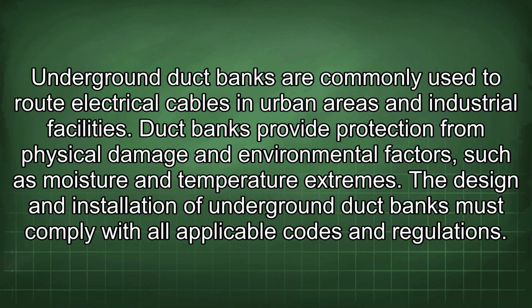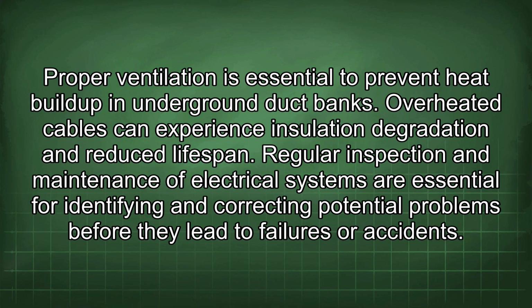Underground duct banks are commonly used to route electrical cables in urban areas and industrial facilities. Duct banks provide protection from physical damage and environmental factors, such as moisture and temperature extremes. The design and installation of underground duct banks must comply with all applicable codes and regulations. Proper ventilation is essential to prevent heat buildup in underground duct banks. Overheated cables can experience insulation degradation and reduce lifespan.